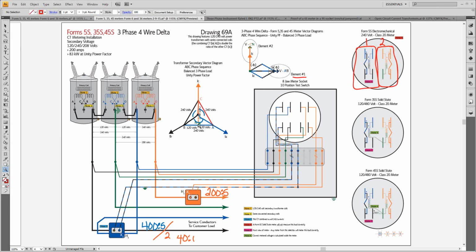Or if I want to get to 208 the other way, I can go across this coil and this coil, across this vector and this vector, to get to the exact same point. So from neutral to this point out here, which is the orange conductor, which could be on either end of that jumper. I could put it on this end of the jumper or this end of the jumper, because those points here and here are the same electrically, and so as that jumper sits in there, I'm able to get that same point on either side of that. So that's what the voltage across my second potential coil, C to neutral, is across there. So that's the two potential coils.